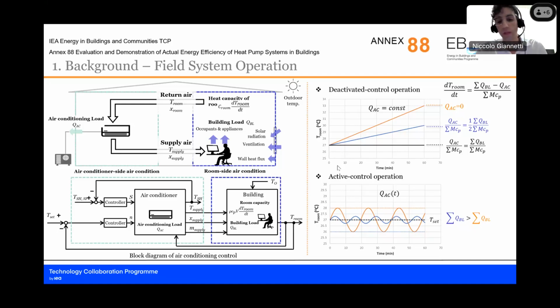During active control operation, the control reacts to the sensor placed in the thermostat, with modulation of control parameters such as the compressor speed or the valve opening for an air conditioner or a vapor compression heat pump, that adjust the operation in a way that cooling capacity is supplied in as precise a manner as possible to maintain the indoor condition as close as possible to a set point. But minimal variations are required for the sensor to sense the indoor temperature variation, and correspondingly the control system responds with the modulation of the system operation.